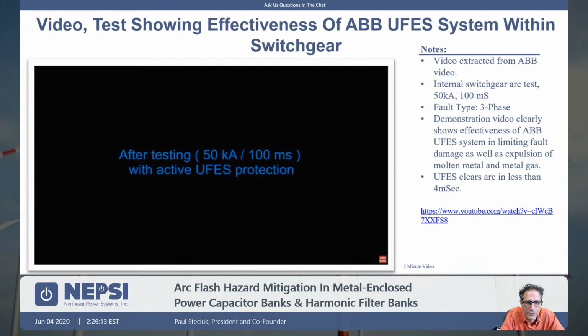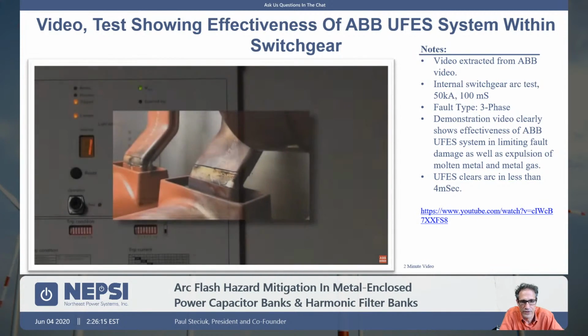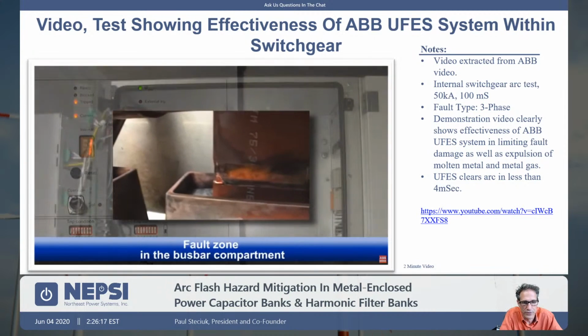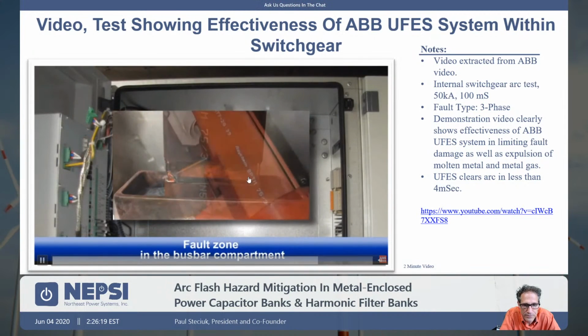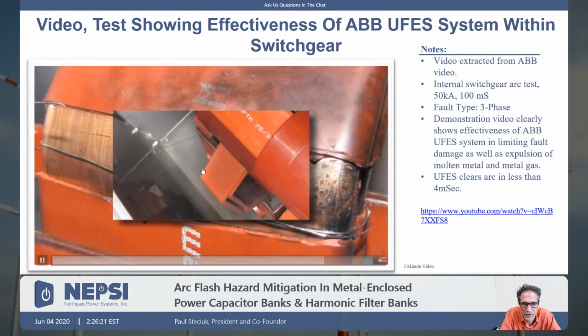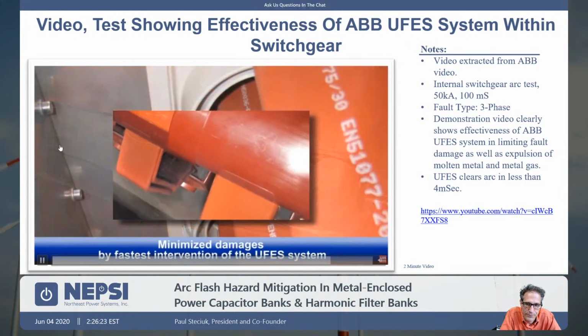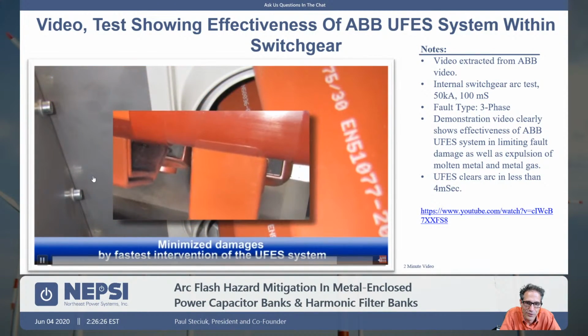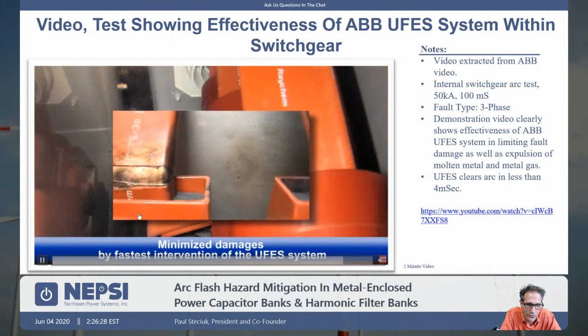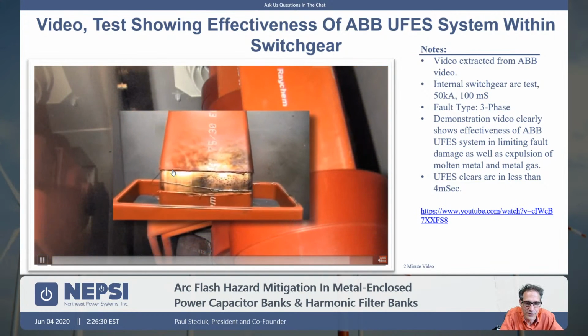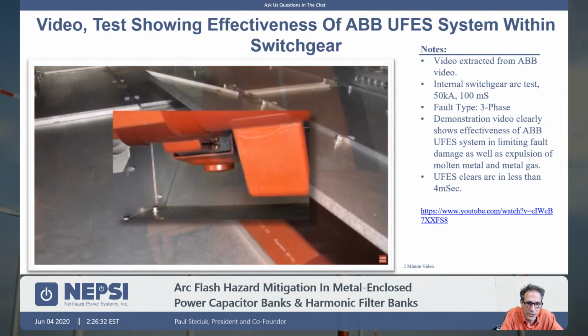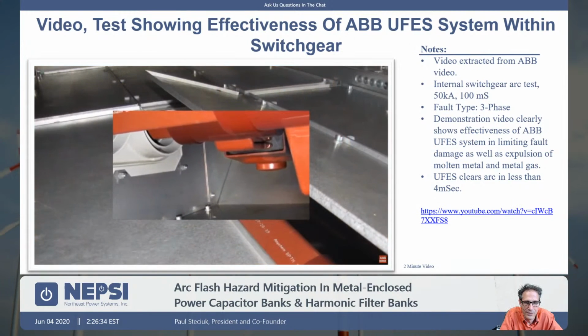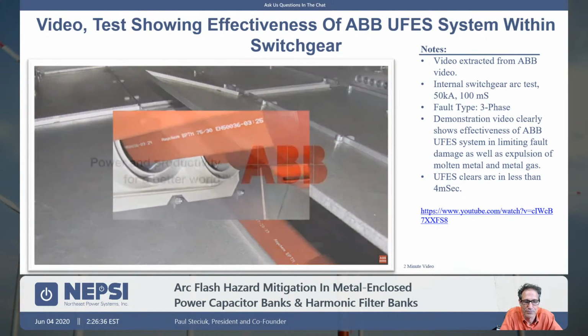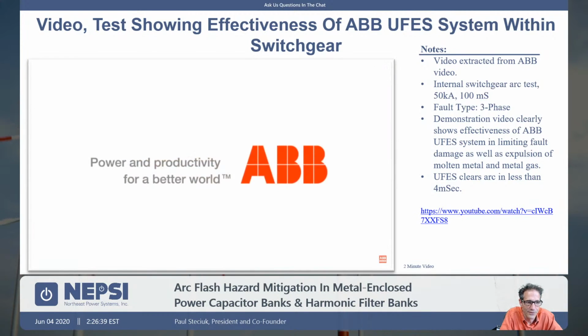So now this video shows the damage related to the system with the ultrafast earthing switch from ABB. You can see here they peeled back the insulation, and there is just a minimal amount of copper burning. In fact, the wire that was used to short the bus bar is still present. There is very little carbon buildup within the bus bar structure. So this literally is a dust off, replace the failed component, and put it back into operation. So something to think about. It's a very, very good system.